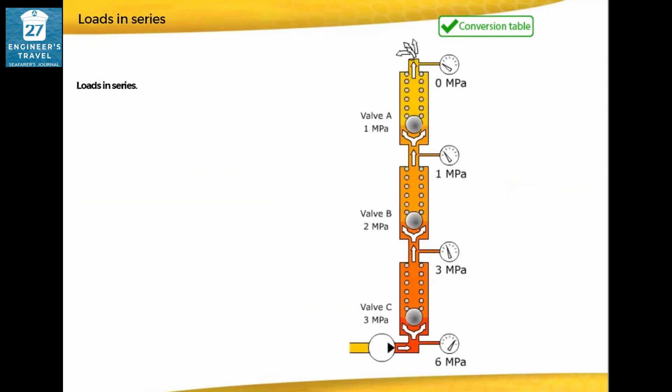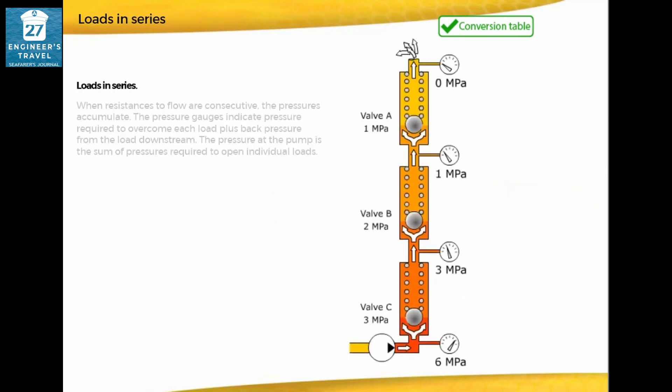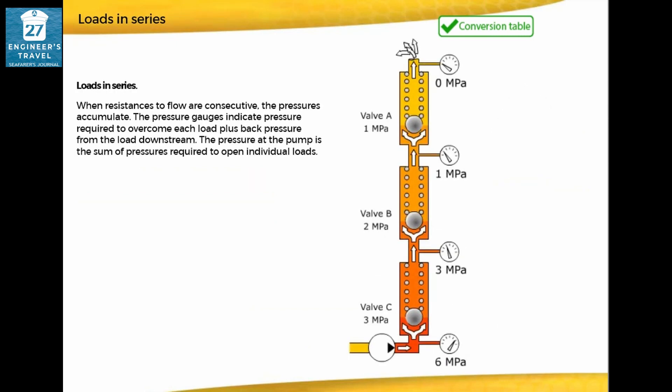Loads in series: when resistances to flow are consecutive, the pressures accumulate. The pressure gauges indicate pressure required to overcome each load, plus back pressure from the load downstream. The pressure at the pump is the sum of pressures required to open individual loads.